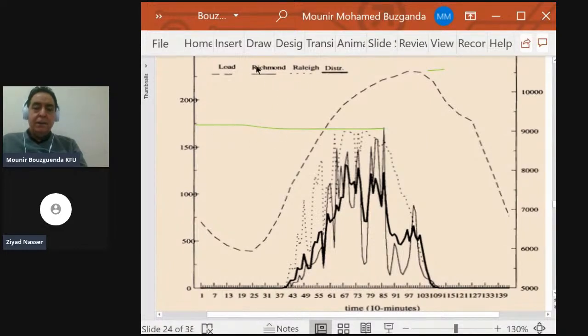And here you see the PV performance for the same day, for each system. You can see this one is very variable, while this smaller one here is less variable. But if I distribute them, using the aggregate, I get a better result, which you can see here by following the red line. There are some drops, but nevertheless it looks smooth, smoother than the other two. That's why you get better, smaller ramping rates for the aggregated PV system.